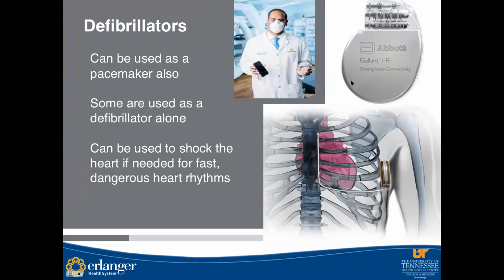We also have defibrillators now that actually look like this, and the defibrillator actually sits right outside of the rib cage, but underneath the skin, and the wire does not actually go into the heart. It sits underneath the skin and is tracked underneath the skin like this. The defibrillator can shock the heart, but in this case, since there's no wire actually touching the heart, the wire cannot deliver an electrical impulse, and therefore cannot regulate a slow heartbeat. So it cannot be used as a pacemaker.